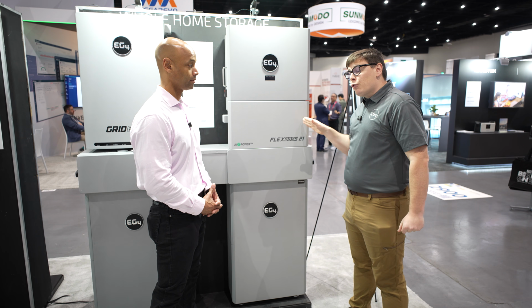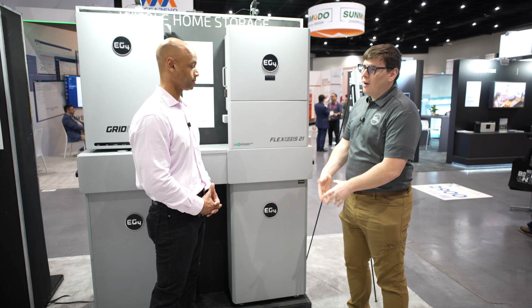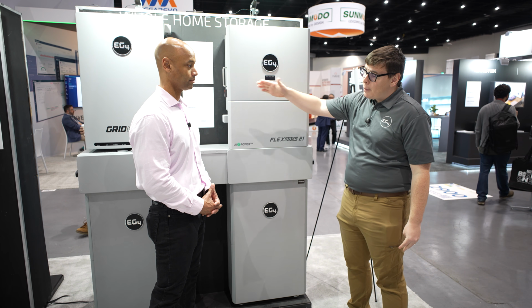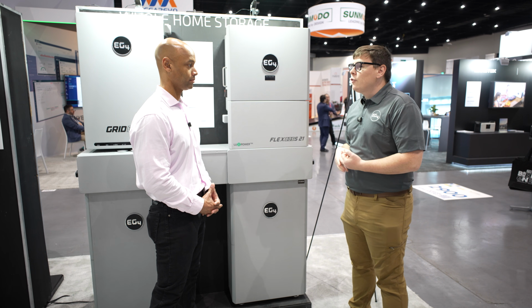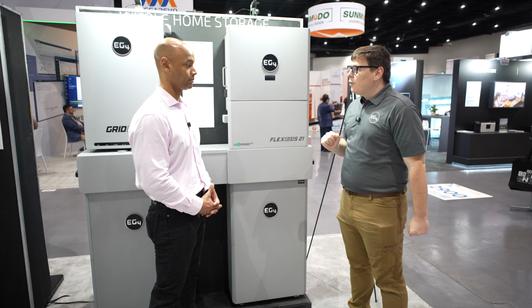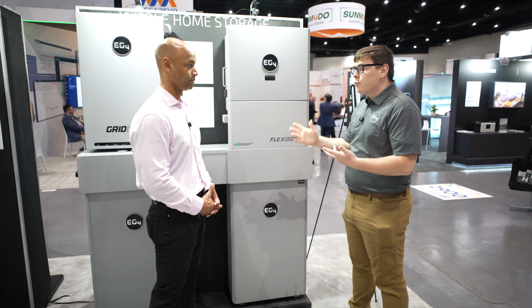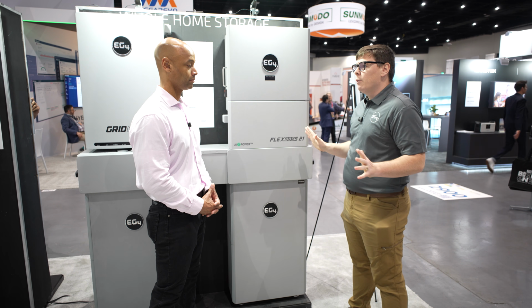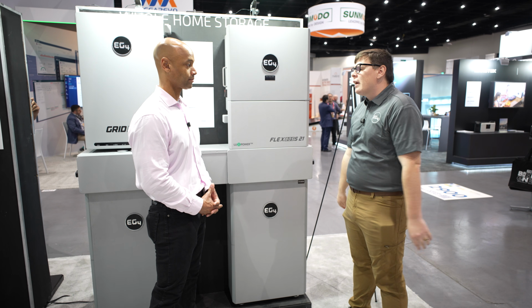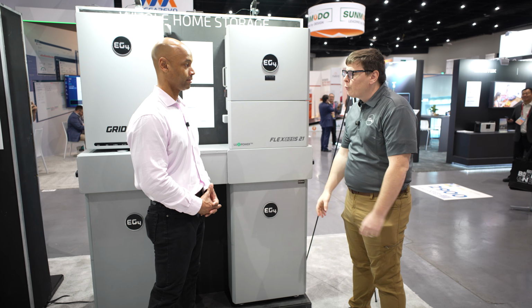It's a 90 amp transfer internally. If you're using it off-grid, you have all full available power without having to buy the GridBoss. But if you're integrating to the grid, you're going to want the GridBoss. It's less money than the transfer switches cost, and it solves about 7 other problems you're going to face if you try to have a 200 amp transfer switch box.